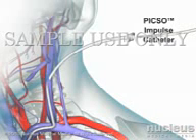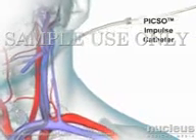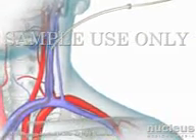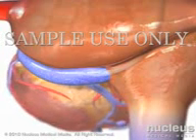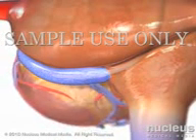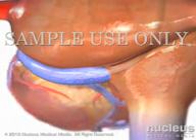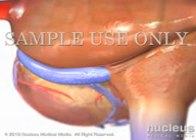The PICSO Impulse catheter is then introduced through the guide sheath. Once the PICSO Impulse catheter is correctly positioned into the coronary sinus using the two marker bands as guidance, the sheath is withdrawn into the right atrium, where it remains for support.